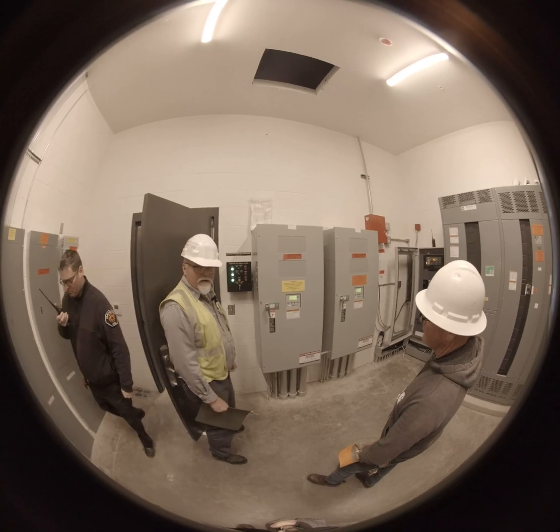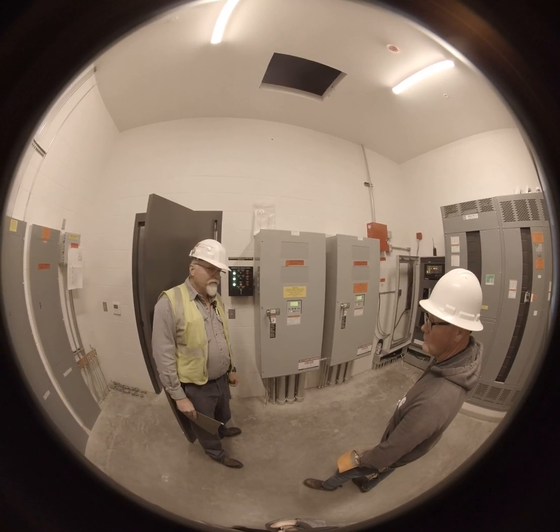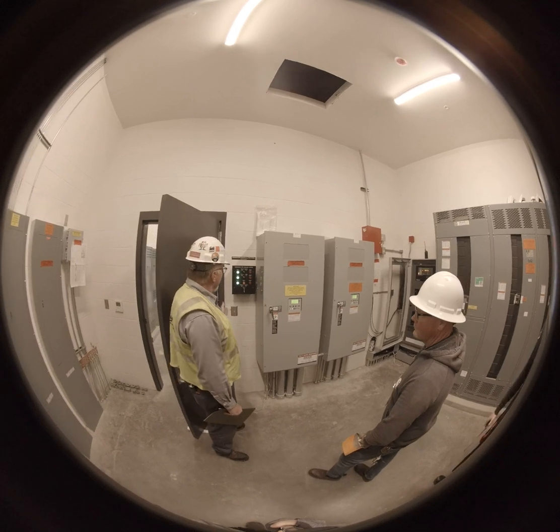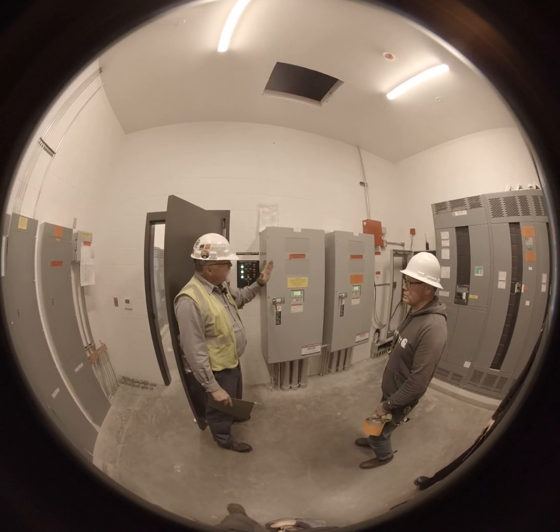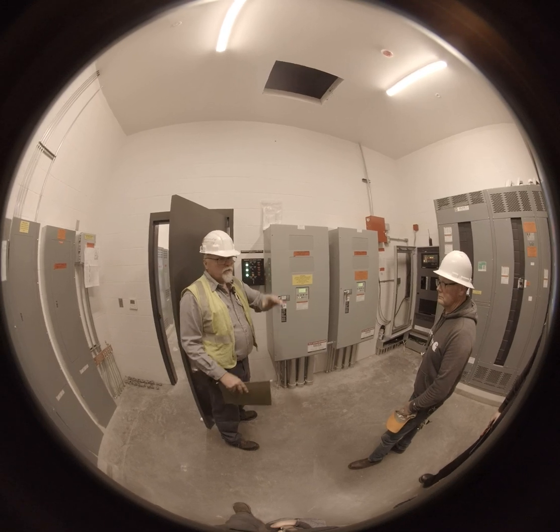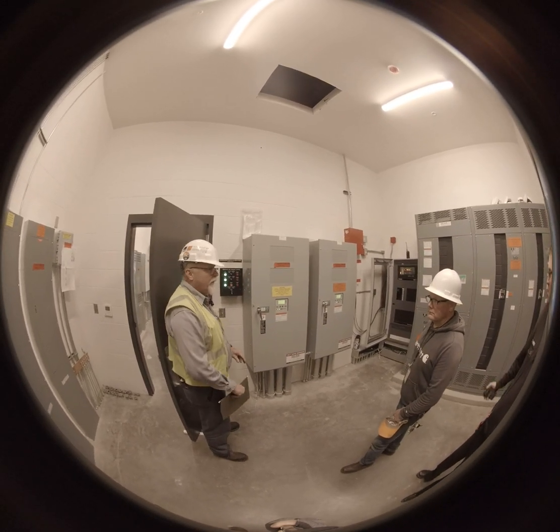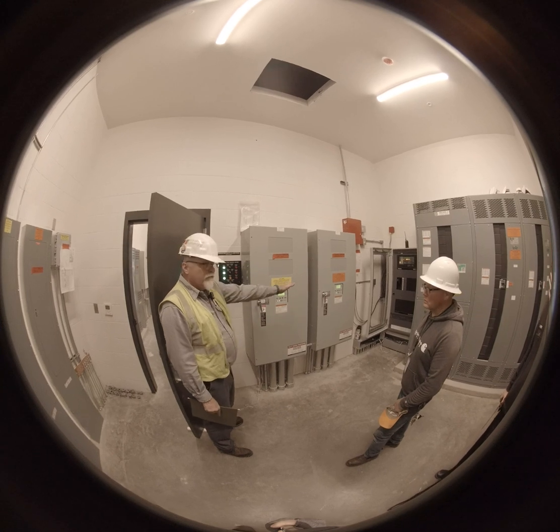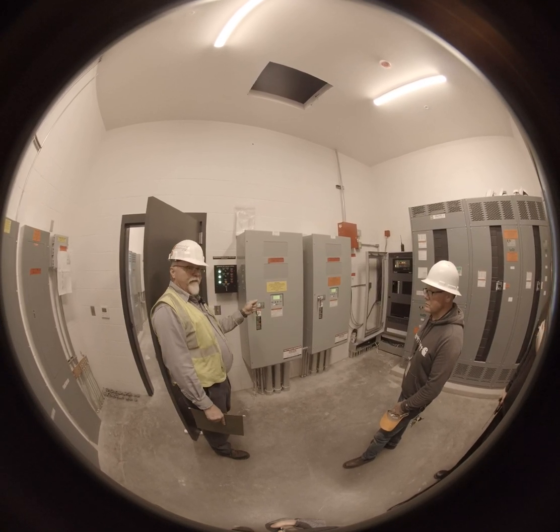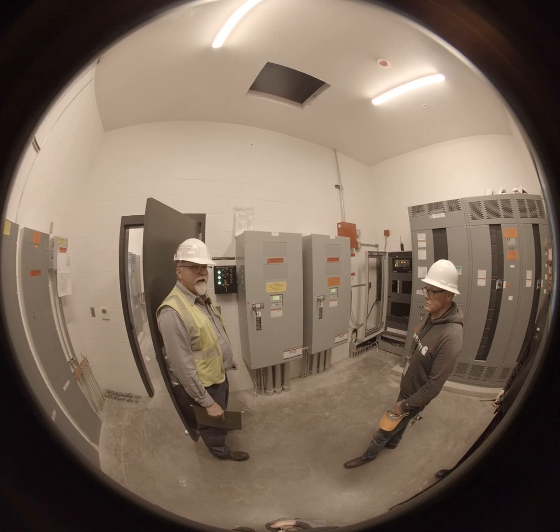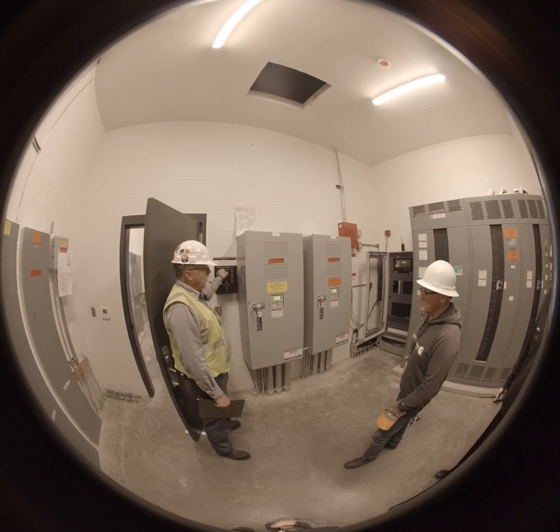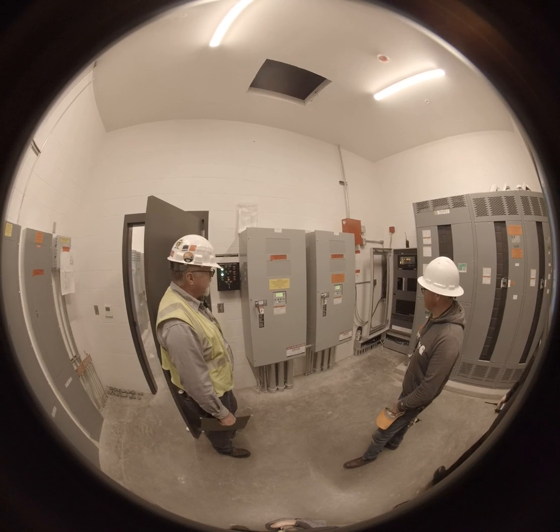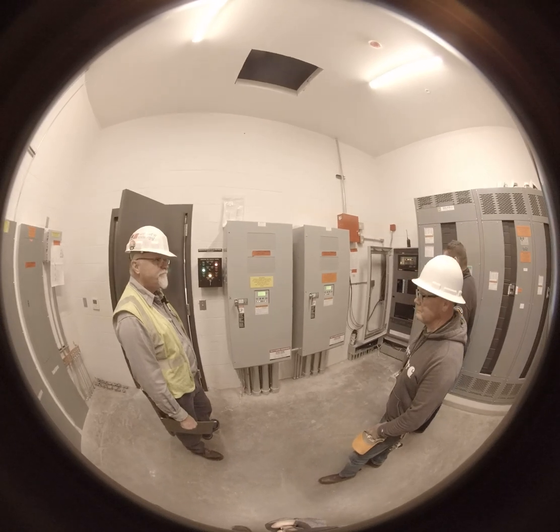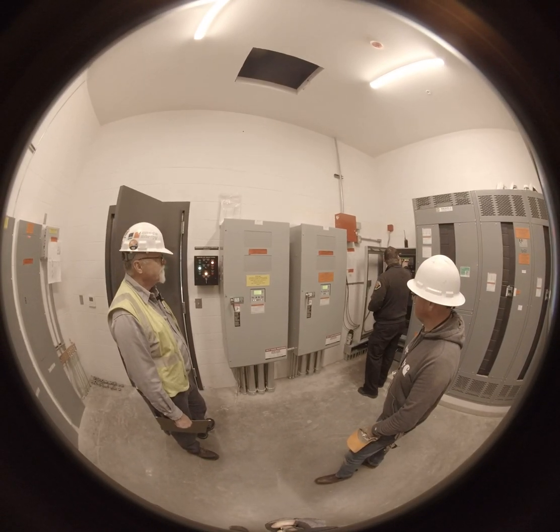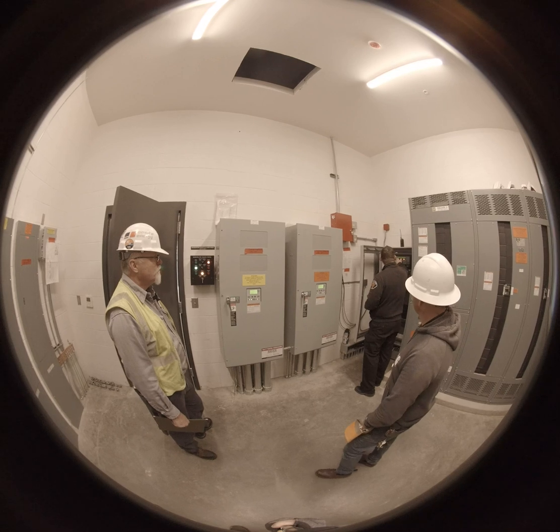Okay. And this is probably a good one for you to see also, because this panel is controlled by you. So what we're going to do is take the emergency panel over, because I'm not sure what's going on with the elevator right now, and I don't want to mess with him. Yeah, the recall's off. So if you came in here and said, I want to put the life safety panel on generator power, we'll go like this. Look over there, we got accessory 17, generator's running, and you're done. There we go. And then we just got supervisory, generator running.